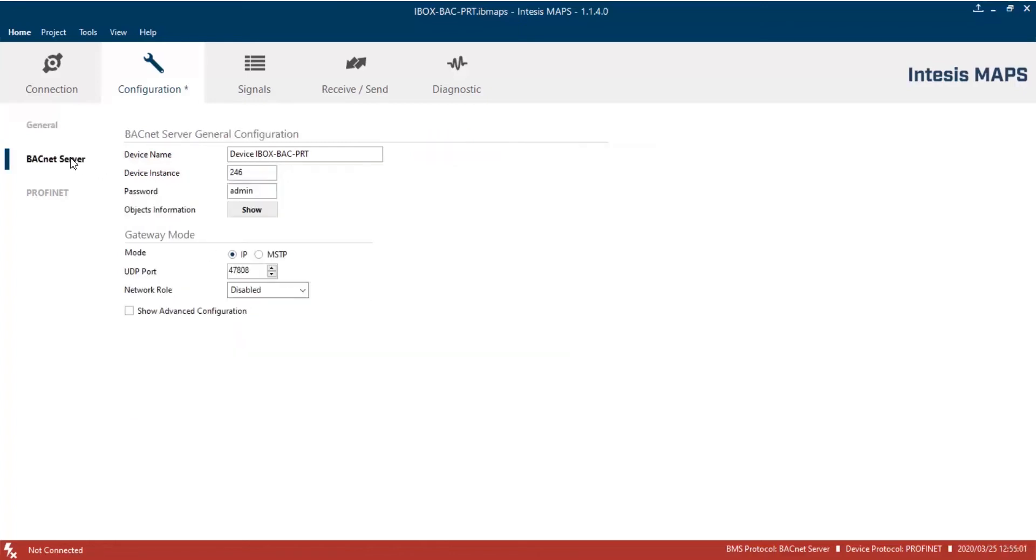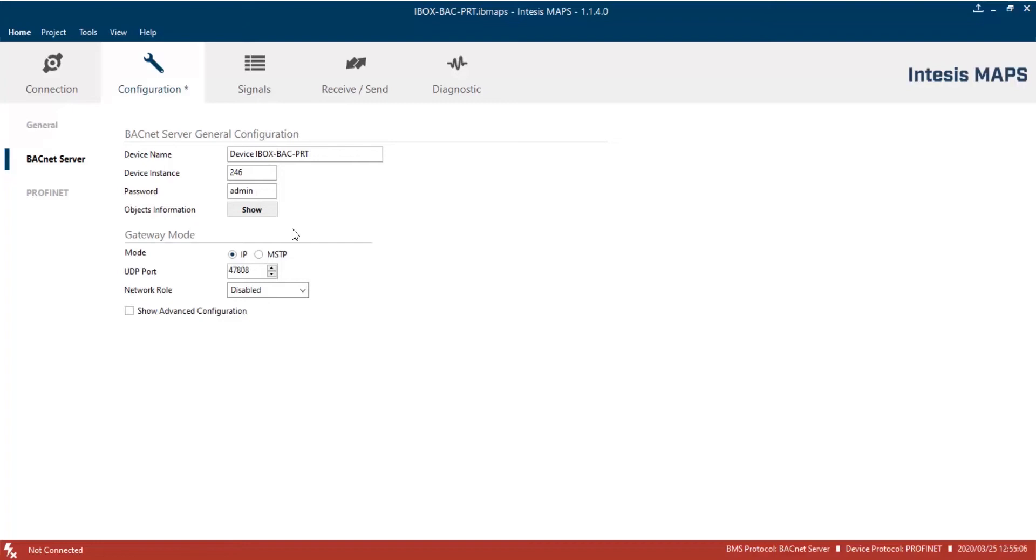On the BACnet server settings, we can change a few options for BACnet IP and MSTP networks. In General Configuration, we can set the device name, which is the name we'll see from the BACnet network. In this case, we'll leave their default value. In the Device Instance field, we'll set the instance number. By default, it's 246 in all Intesis BACnet devices. Password field is a password for BACnet protocol, used to protect some BACnet operations.